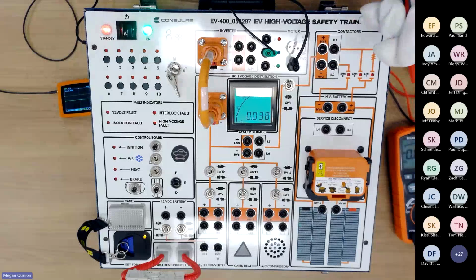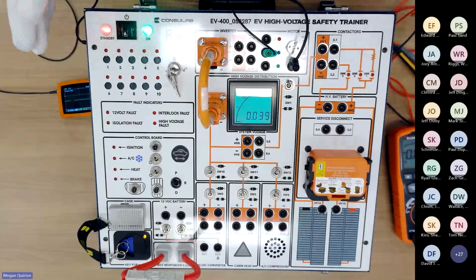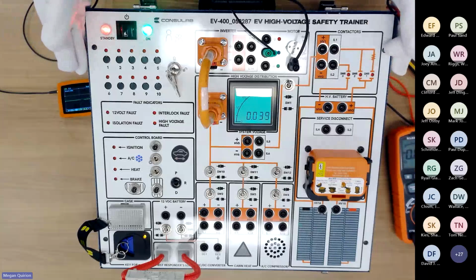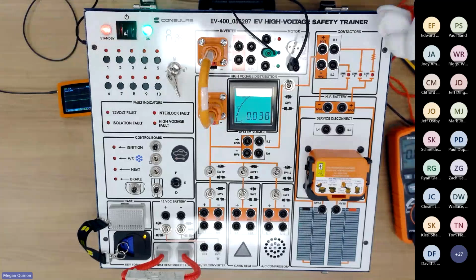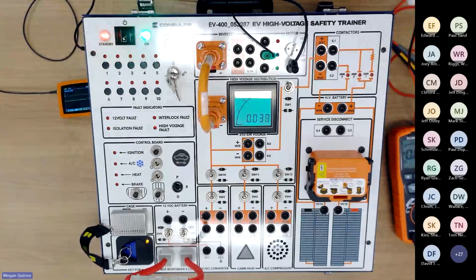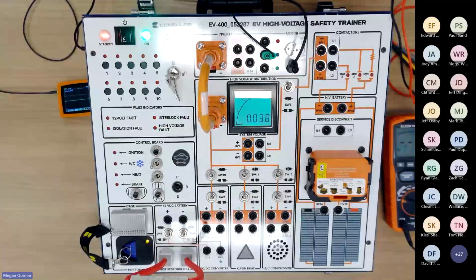So first we pre-checked it. One of the big things when using isolation testers is that you don't just apply 1,000 volts, or 2,500 volts, or even 500 volts to every component. You have to look up manufacturer specifications before doing these tests, and not generically apply voltages just because you think more is better. In this case, we've identified that the unit we're testing is rated for 1,000 volts, so we'll use a 1,000 volt measurement to stress the system on this trainer. We're going to test the PTC.